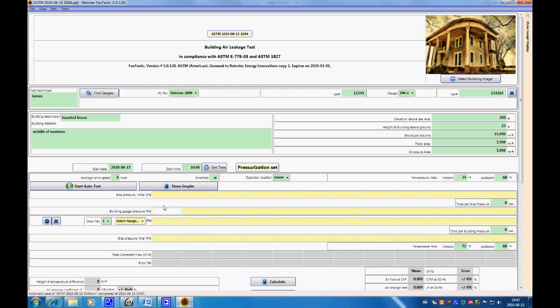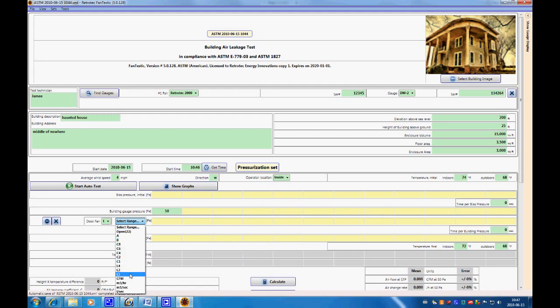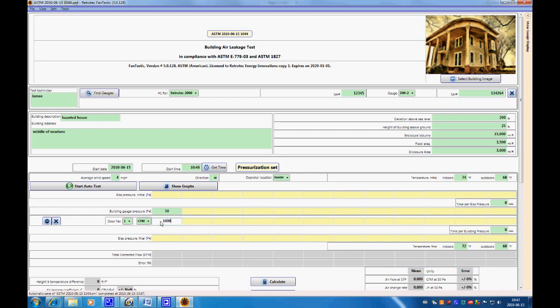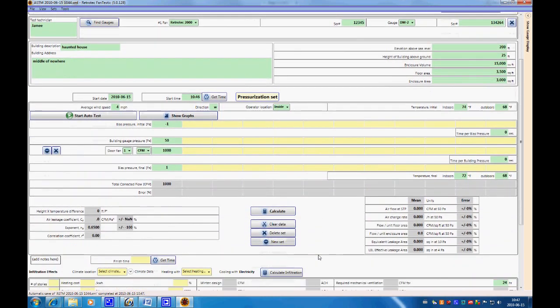Because we're doing a manual single point test, we're going to be adding the data ourselves — just one building pressure. Let's say we're testing to a pressure of 50 pascals, and we want to choose a range. Generally when you choose a range, you're looking at which range plate is on the fan at the time. But because we're adding the data ourselves, we're going to add in a CFM value — let's say about 1,000. We can say there's a bias pressure checked before the test of negative 1, and afterwards a bias pressure of 1. Then we click Calculate, and the results show up in the grey squares, which are the calculated fields.